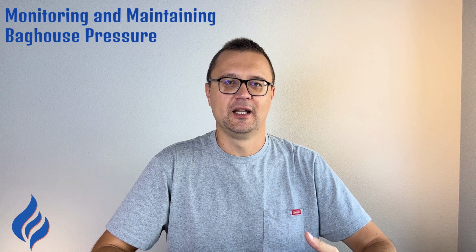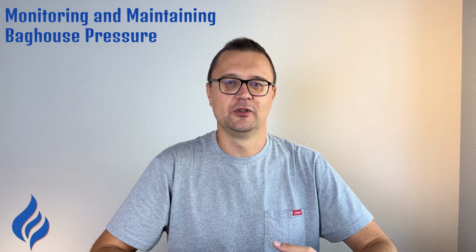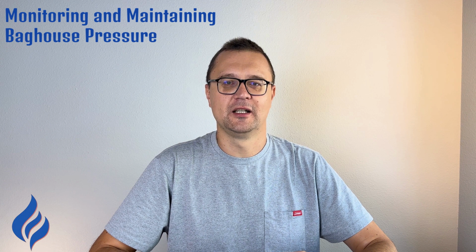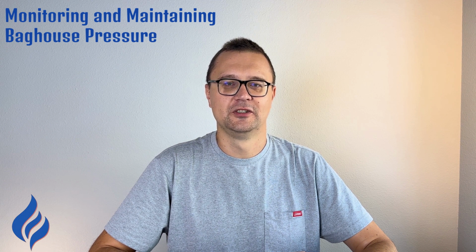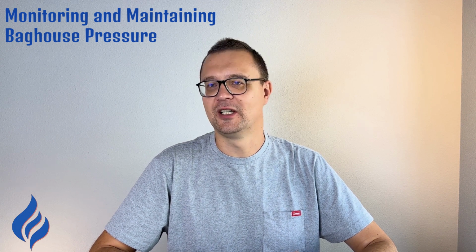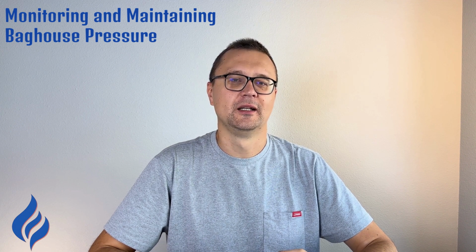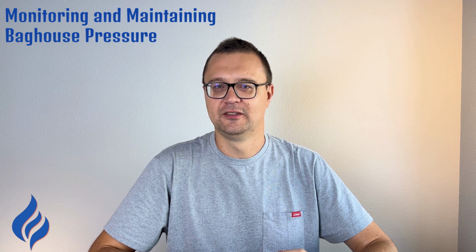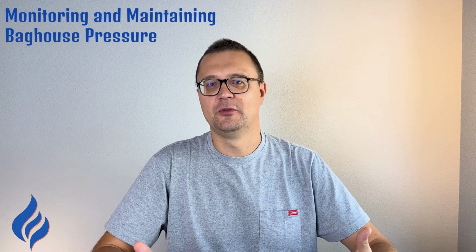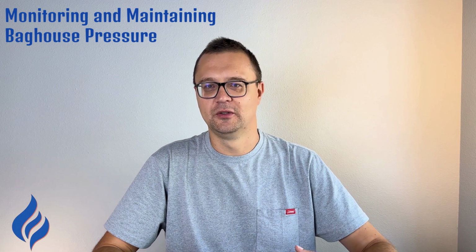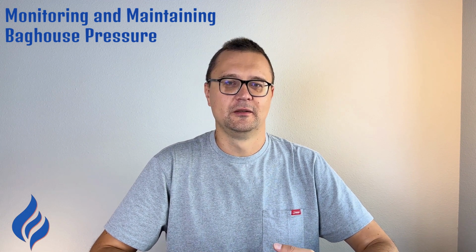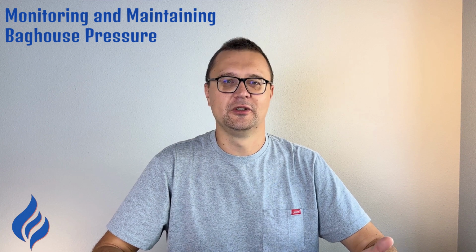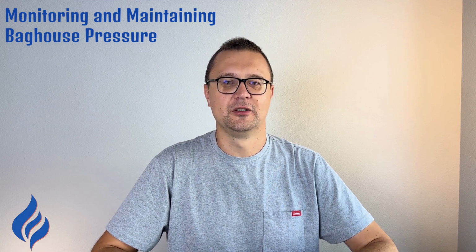Monitoring and maintaining baghouse pressure. So how do you keep everything running smoothly? Monitoring pressure and static levels is the key to optimizing your baghouse system. Install pressure gauges that measure differential pressure and keep an eye on any major changes. If pressure starts creeping up, it's time to check your filters for clogging or possible air leaks. Also, don't forget about routine maintenance. Regularly cleaning out filters, checking fans, and performing system inspections will keep your pressure levels where they need to be.